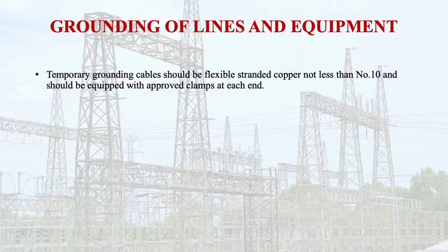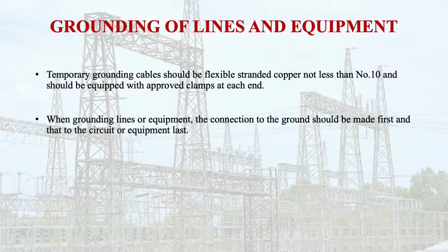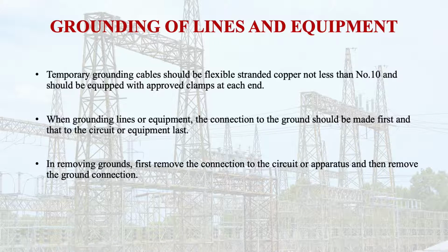Temporary grounding cables should be flexible stranded copper and should be equipped with approved clamps at each end. Grounding cable should be inspected before each use. When grounding lines or equipment, the connection to the ground should be made first, and that to the circuit or equipment last. First of all, the ground connection should be made, and only then the other connections. When you are removing the grounds, remember first remove the connections to the circuit or apparatus, and then remove the ground connection.